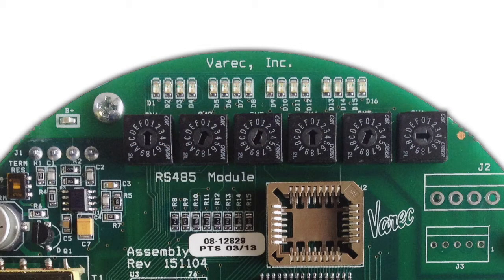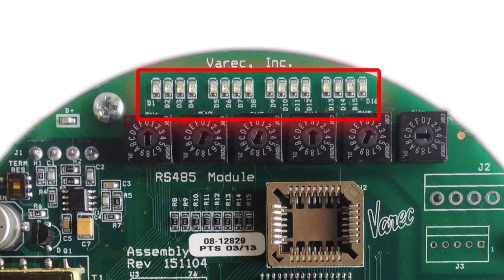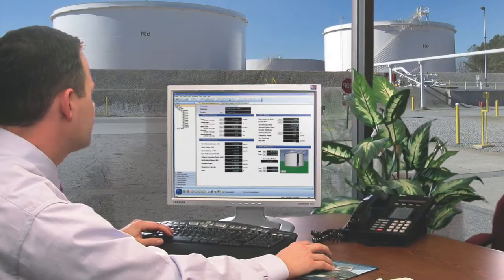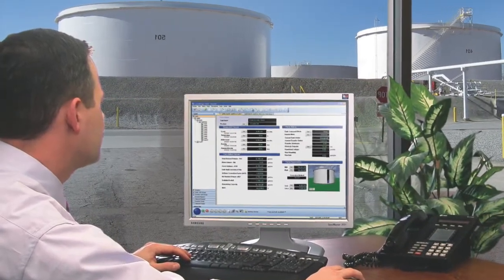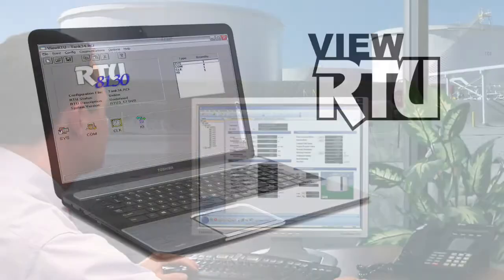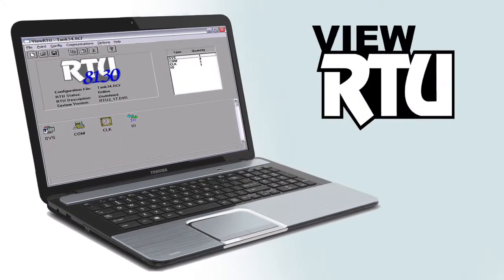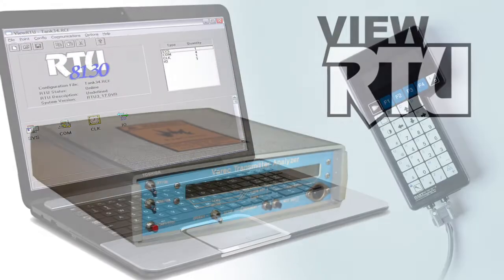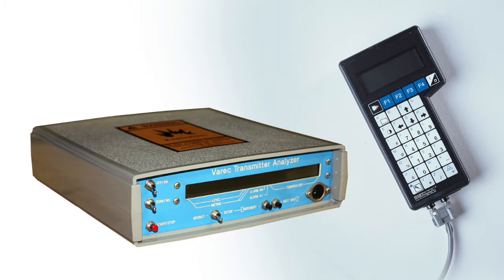There are four ways to view the current configured level in the encoder. We'll use the diagnostic LEDs built into the encoder electronics board. But you can use a host system such as Fuels Manager, you can connect a laptop to the transmitter running ViewRTU software, or you can use a handheld transmitter analyzer. Keep in mind that some analyzers have limits. For example, if you're using the VTA-1000, you'll get an invalid level reading if your tank's level is above 78 feet.